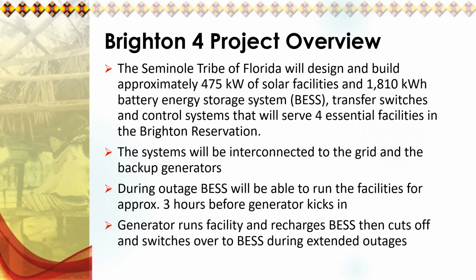Now here's the Brighton 4 project overview. In the Brighton project, the Seminole tribe will design and build approximately 475 kilowatt solar facilities and a 1,810 kilowatt hour battery energy storage system. It will include transfer switches and a control system that will serve 4 essential facilities in the Brighton Reservation. The systems will be interconnected to the grid and to the backup generators. During an outage, the BESS will be able to run the facilities for at least 3 hours before the generator kicks in. Then the generator will run the facility and recharge the BESS, then cut off and switch back to BESS during extended outages.